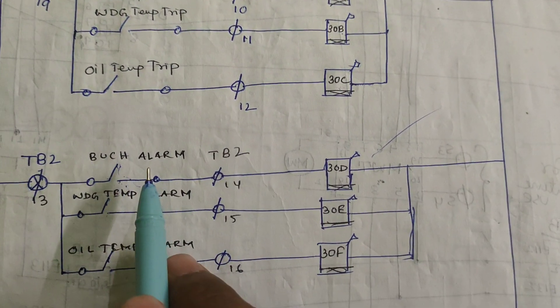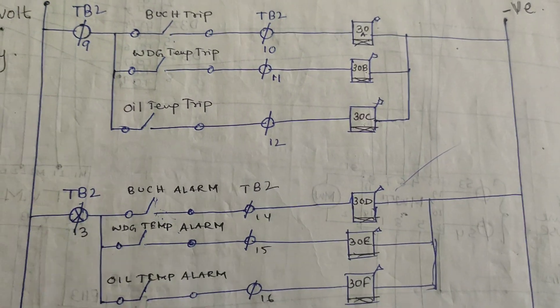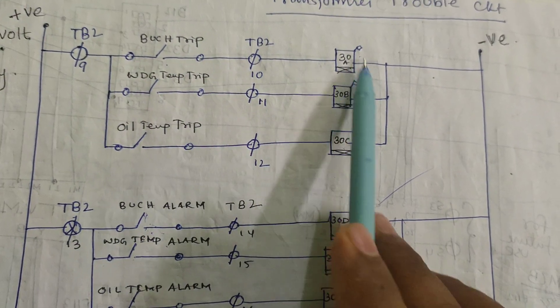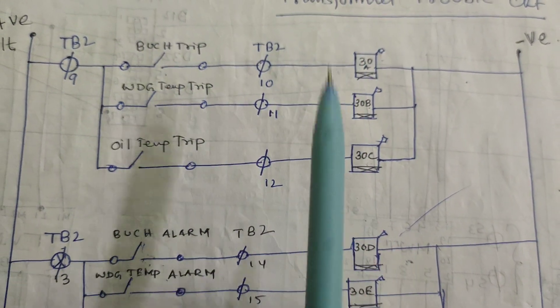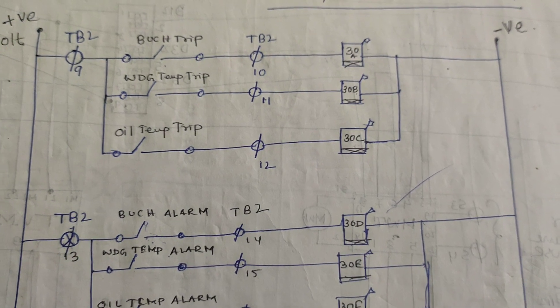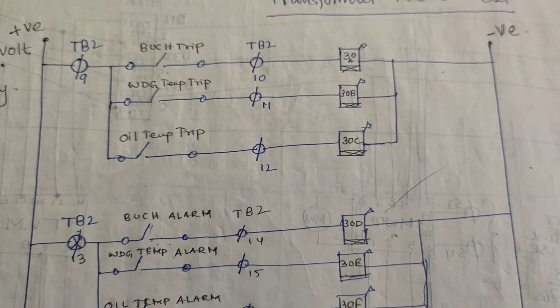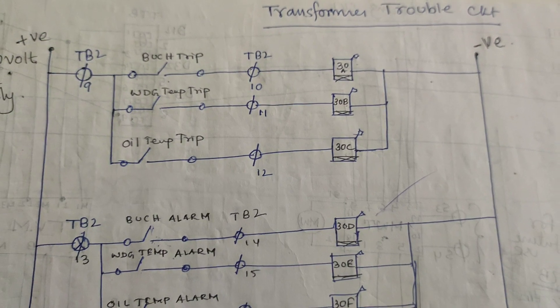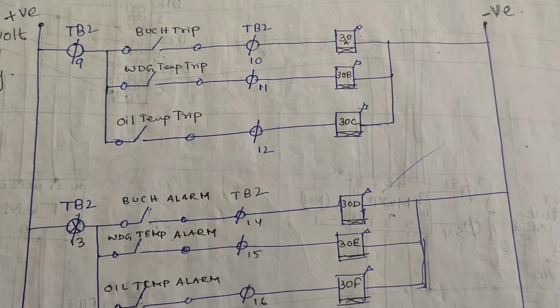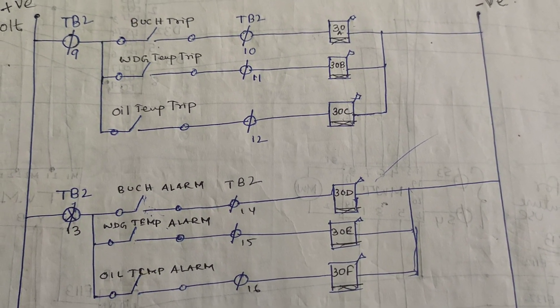If the Buchholz alarm is not attended to properly, more gas will be generated and the Buchholz trip will activate. The 30A flag drops and the breaker trip coil is activated, isolating the transformer. For a 132/33kV 50 MVA transformer or a 220/132kV 160 MVA transformer, the 132kV circuit breaker trips via the 86 relay and the 33kV side also trips.